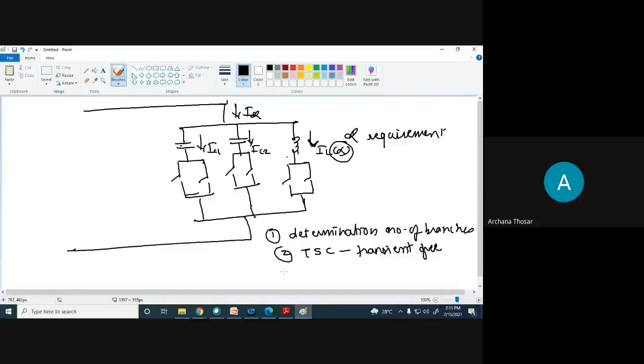Variation of current in the thyristor controlled reactor by firing angle. So you need to find the appropriate delay or firing angle which decides the current flowing through this TCR. So there are two parts: one is the TSC and the other is the TCR, and hence the control system becomes very important here.